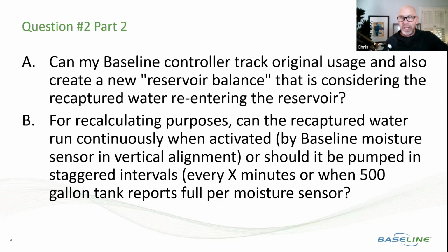So we know, based on the pressure transducer values in the tank, what the volume of water is in that tank. And we can tell it to create those start, stop, or pause conditions based on that amount of volume.